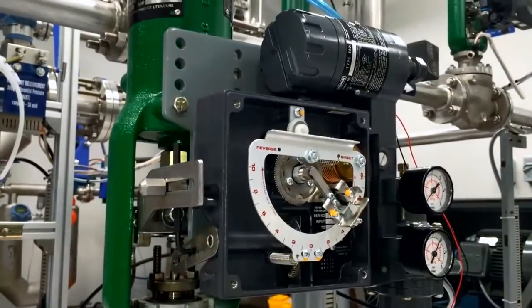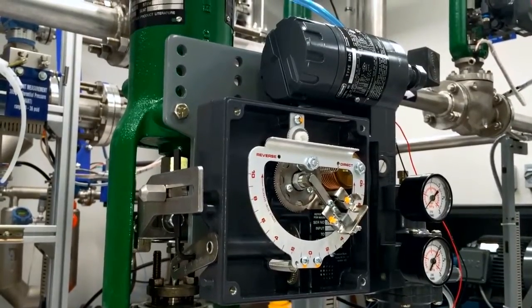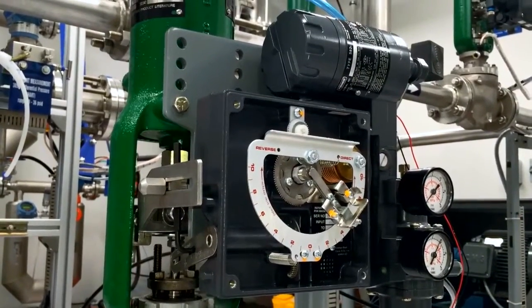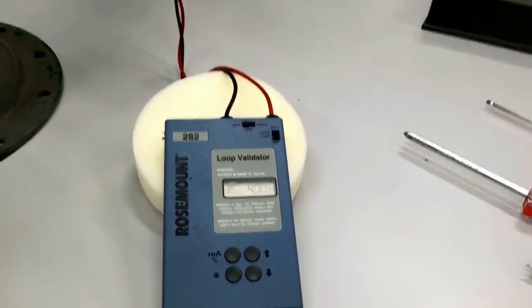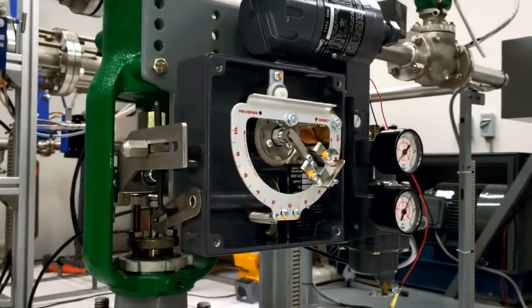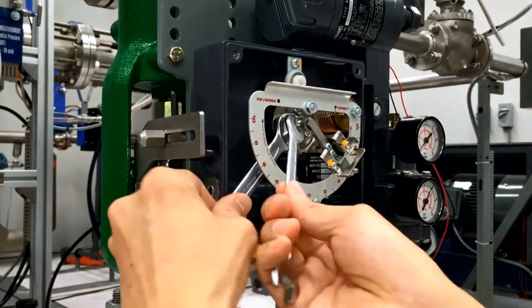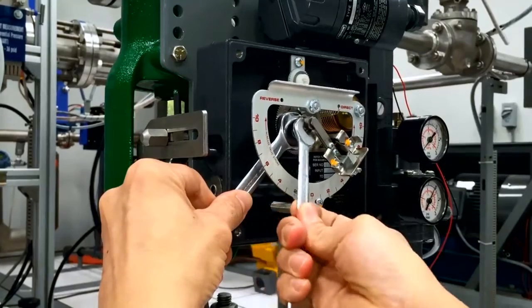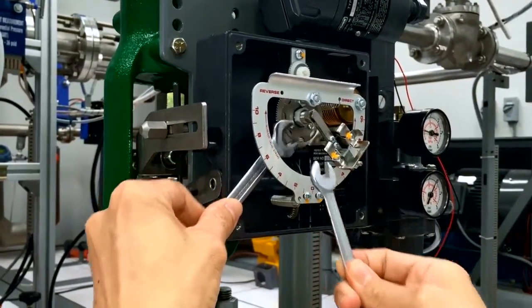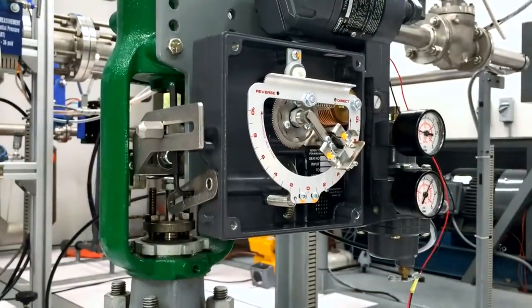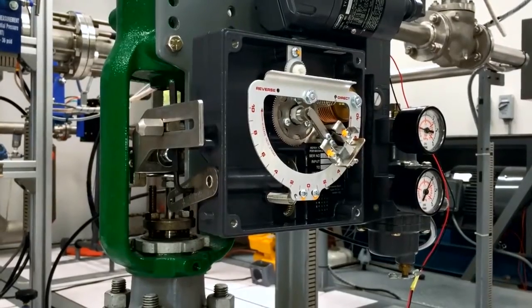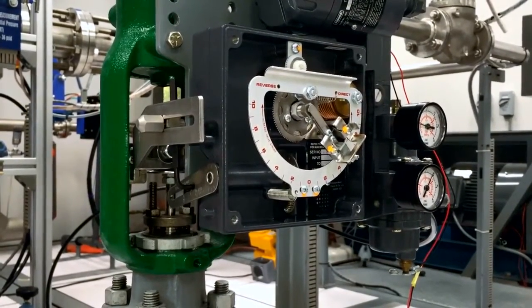To start calibration, we first apply an input signal equal to the low value of the input signal range, in this case 4 milliampere. We first loosen the nozzle lock nut and adjust the nozzle for zero valve position. Changing the nozzle position is intended only as a means of zero trim adjustment. Whenever nozzle position is changed, the zero reference point is changed.